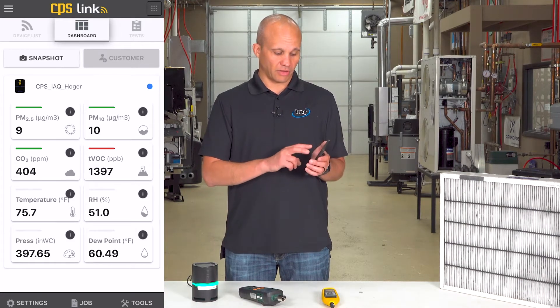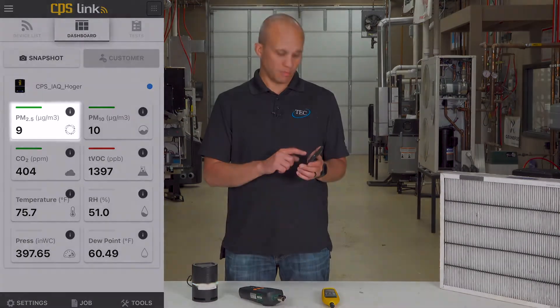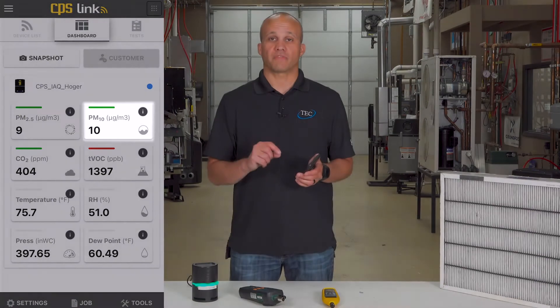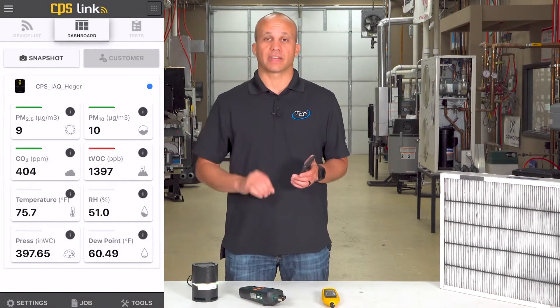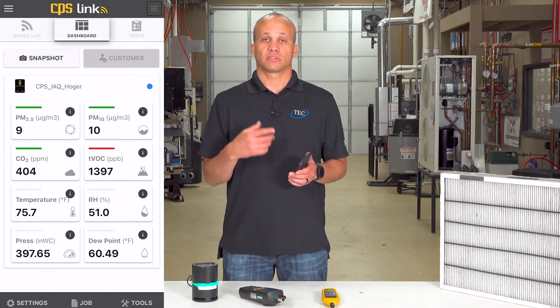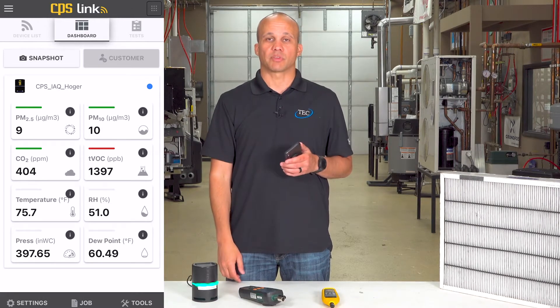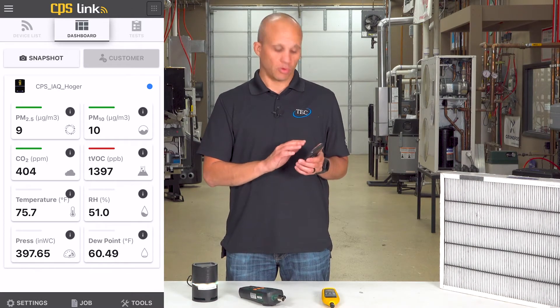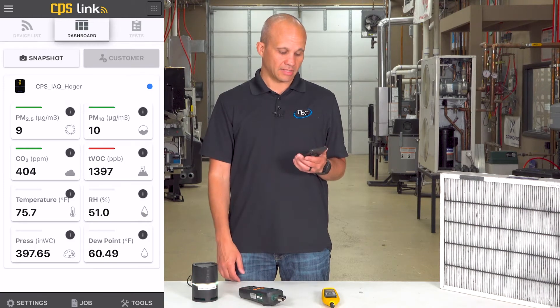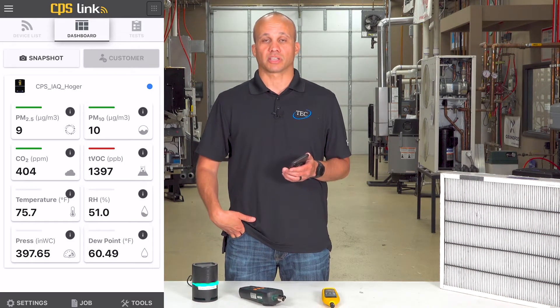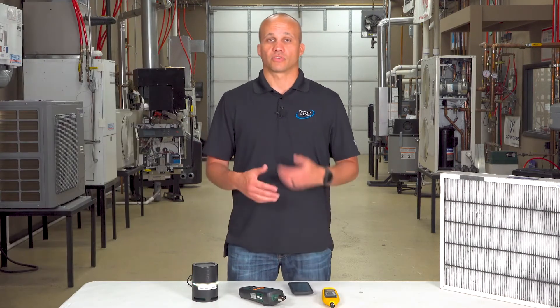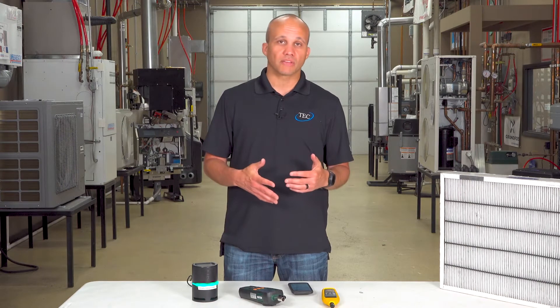The other measurements on here are particulate counts: PM2.5 and PM10. PM2.5 means 2.5 microns — a really tiny dimension — and PM10 is 10 microns. The PM10 measurement indicates how many larger particles are floating in the air, and PM2.5 indicates the smaller ones. Right now we're at 9 and 10, which are very low numbers. But if there's manufacturing connected to your office building, or activities like smoking, those would add particulates to the air and need to be addressed.